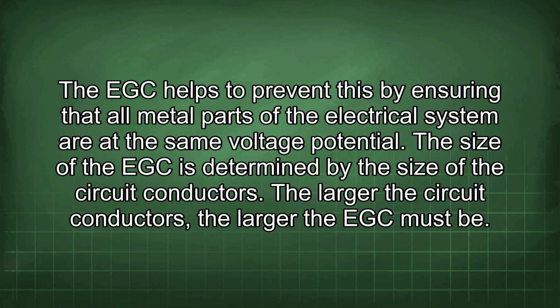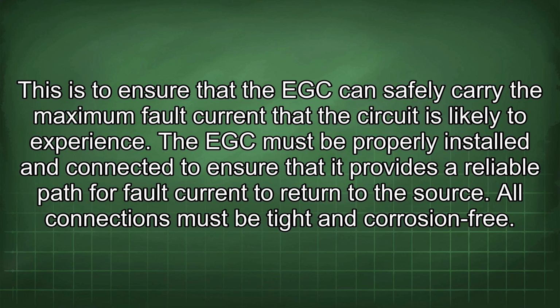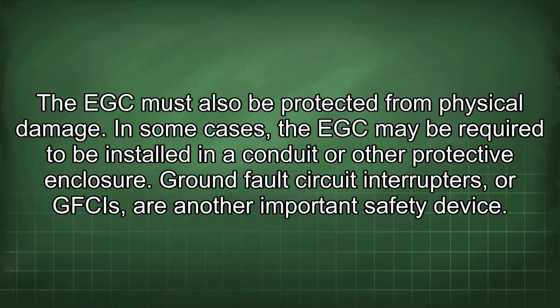The size of the EGC is determined by the size of the circuit conductors. The larger the circuit conductors, the larger the EGC must be. This is to ensure that the EGC can safely carry the maximum fault current that the circuit is likely to experience. The EGC must be properly installed and connected to ensure that it provides a reliable path for fault current to return to the source. All connections must be tight and corrosion-free. The EGC must also be protected from physical damage. In some cases, the EGC may be required to be installed in a conduit or other protective enclosure.